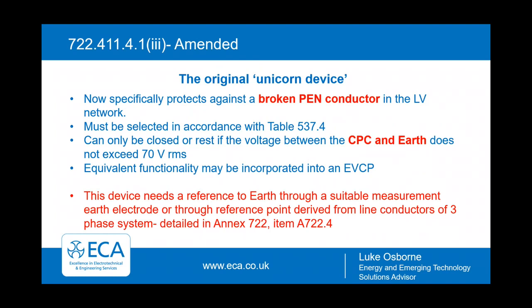But it could also, and this wasn't in the previous iteration of the wiring regulations, it could also take this reference through a point derived from the line conductors of a three-phase system. And this is detailed in Annex 722.4.